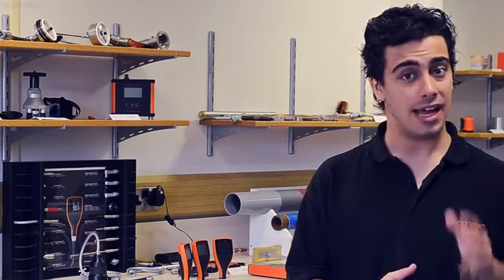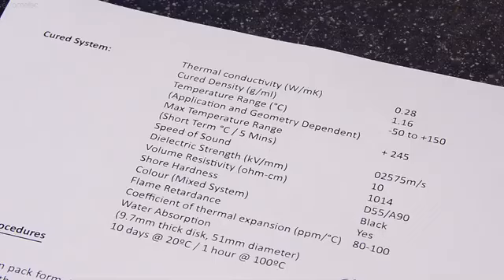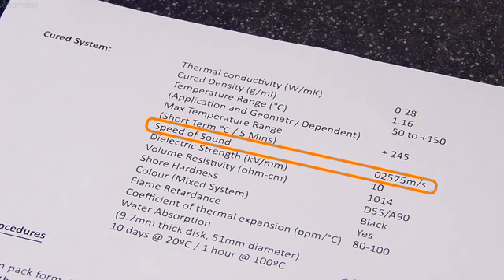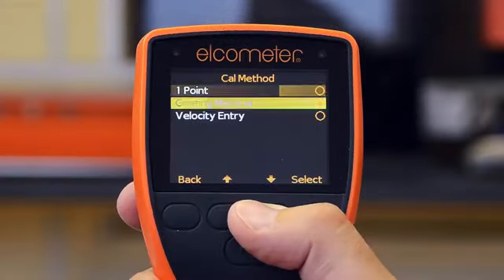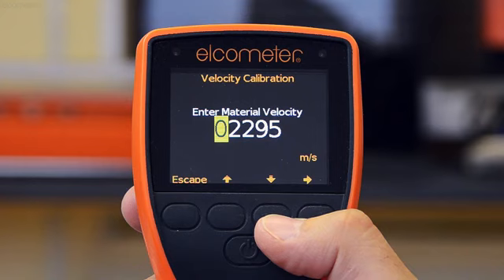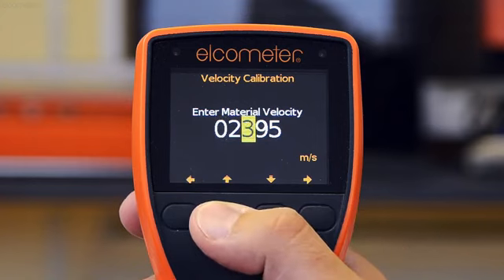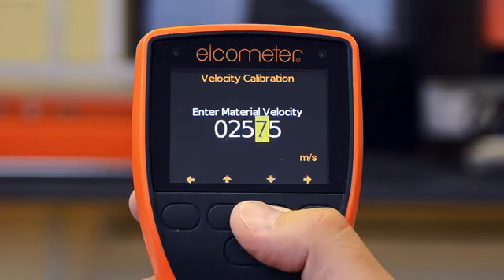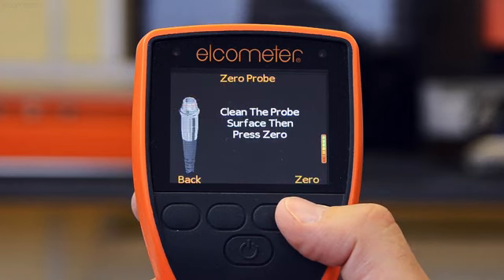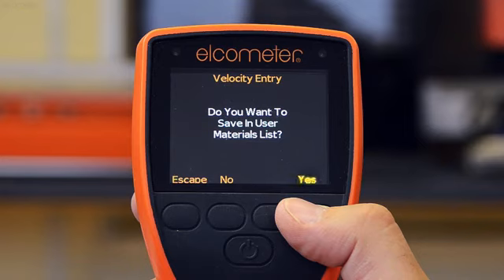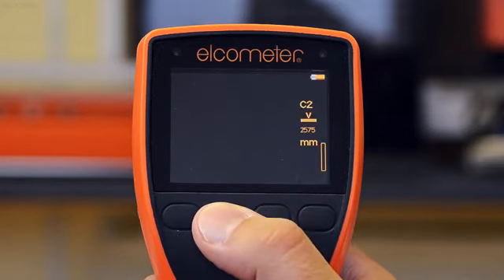But how do you go about creating a known thickness of the coating? And how do you find out what its speed of sound actually is? If the coating manufacturer has included the speed of sound on the product datasheet, then simply select the velocity entry calibration method from the calibration menu and insert the speed of sound. The gauge will then ask you if you wish to save the coating in the material library for use at a later date. If you do, press yes and follow the on-screen instructions. By pressing no, the gauge is calibrated and returns to the reading screen.